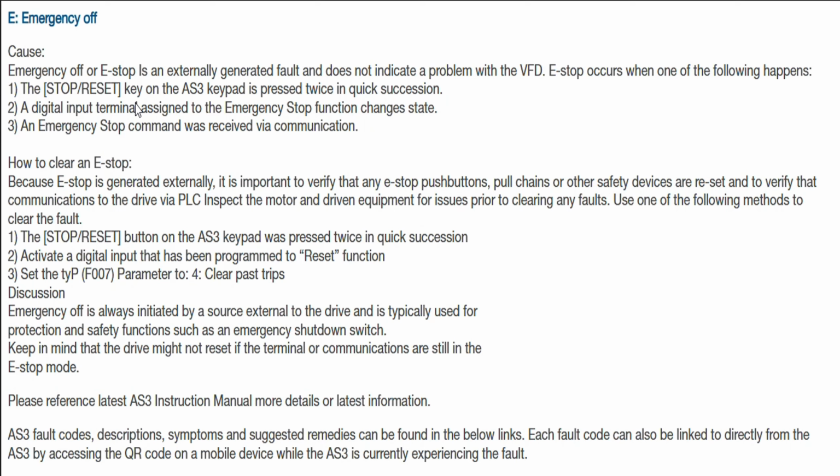Your VFD is okay. It is about the wiring. So your wiring of the VFD is maybe broken in between, or it could be that the emergency button is pressed, or any output from the PLC is given. That also could be the cause of the off.